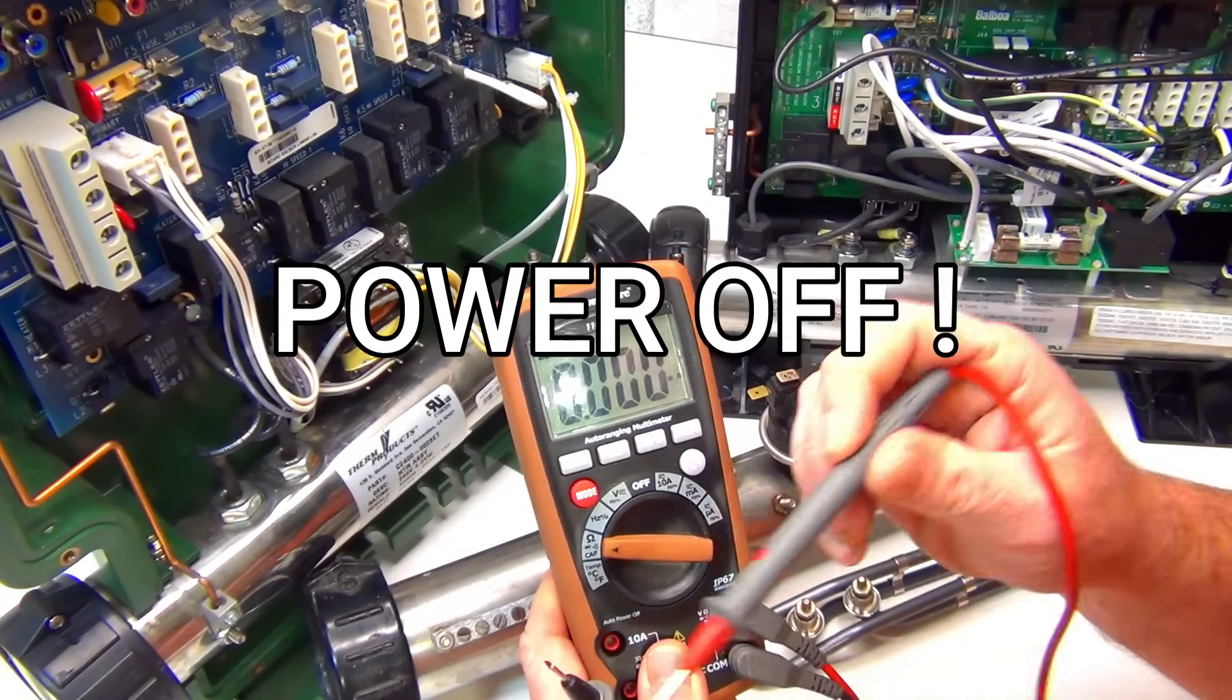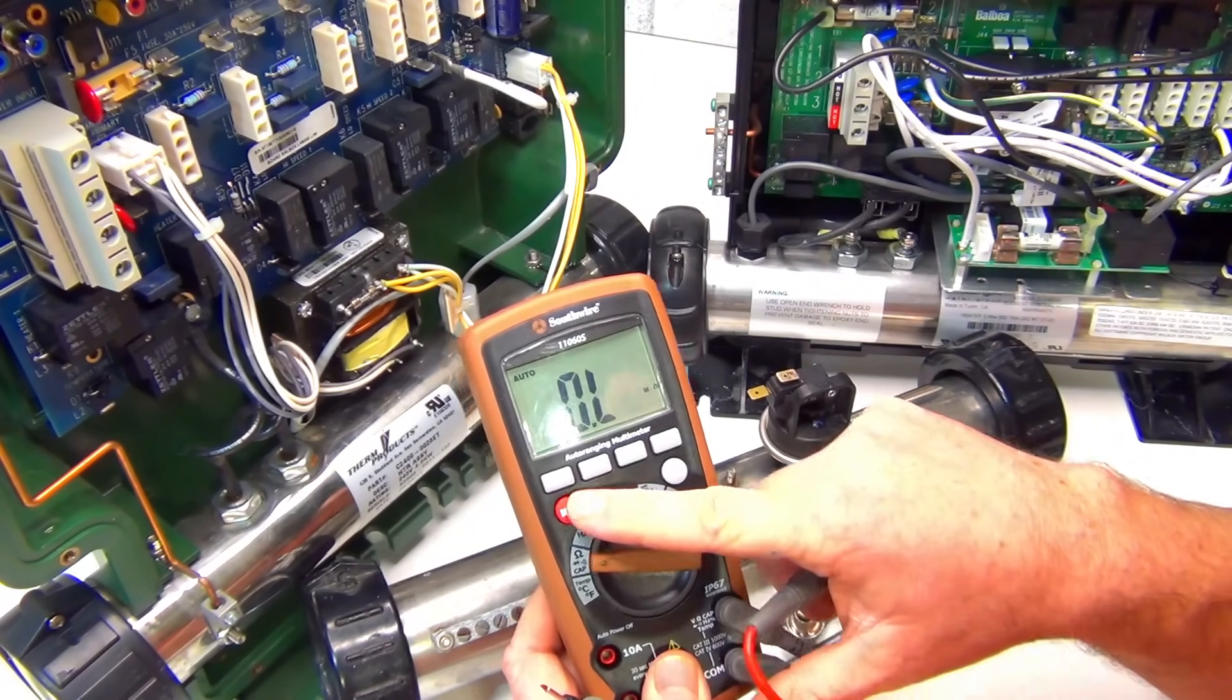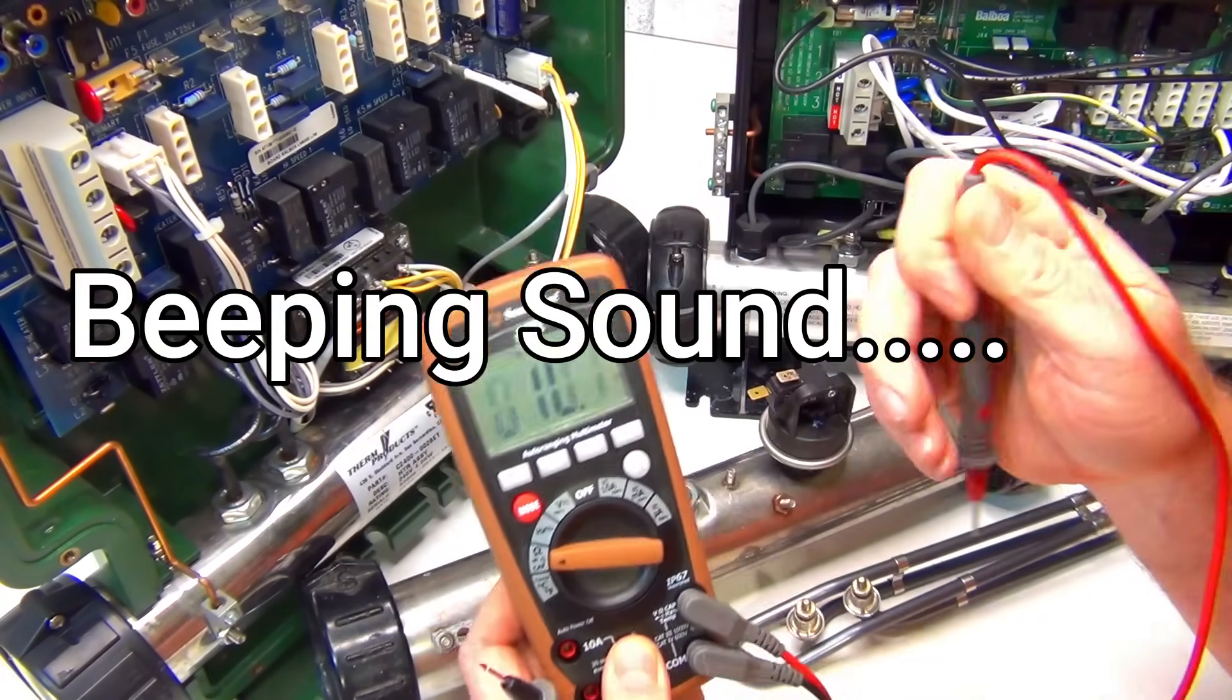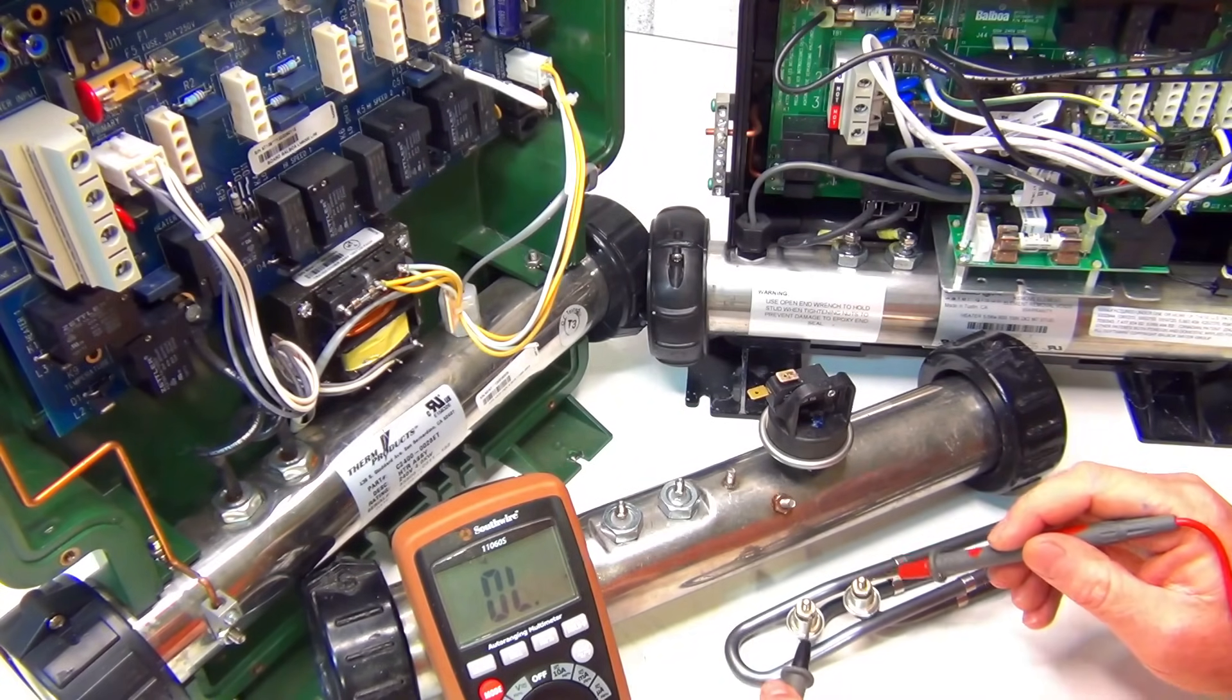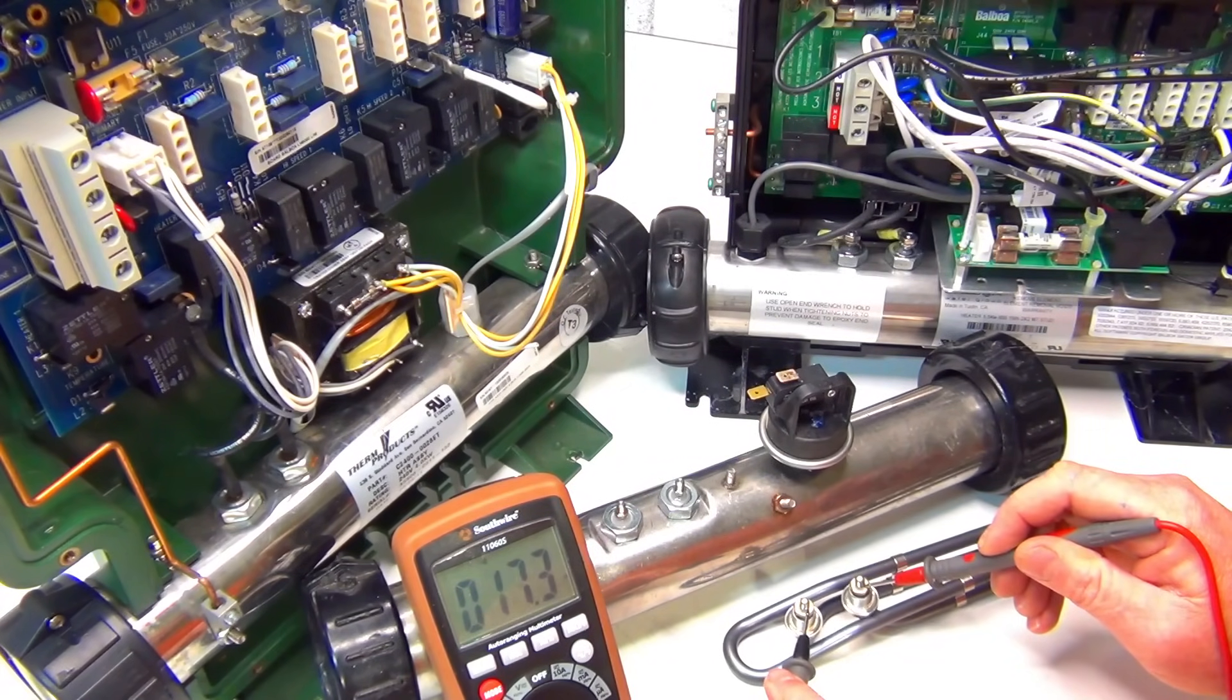So we're going to test continuity now. For continuity, for my meter anyway, the two leads touch and you get that beep. So I'm going to keep it at the ohm symbol and the continuity. So we put together, you hear a beep. I'll show you what it looks like here. So we test the element, should beep, and it should go between 10 and 11.